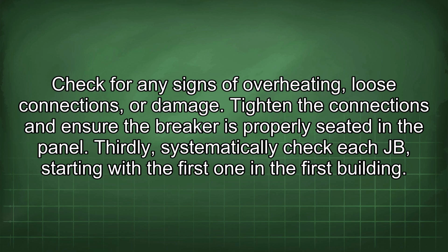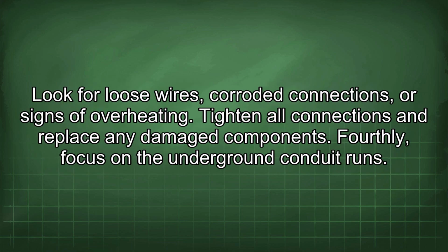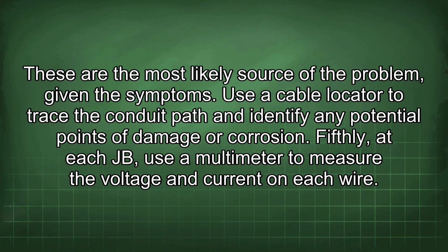Thirdly, systematically check each JB, starting with the first one in the first building. Look for loose wires, corroded connections, or signs of overheating. Tighten all connections and replace any damaged components. Fourthly, focus on the underground conduit runs. These are the most likely source of the problem, given the symptoms. Use a cable locator to trace the conduit path and identify any potential points of damage or corrosion.